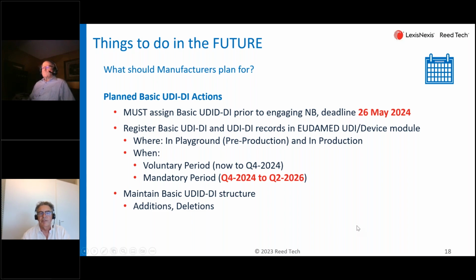For now, there's a voluntary option to do that. It is expected that EUDAMED will be ready in the future, which probably triggers a mandatory period of registration of new data after the fourth quarter of 2024, and after the second quarter of 2026, everything must be in EUDAMED and be kept up to date.